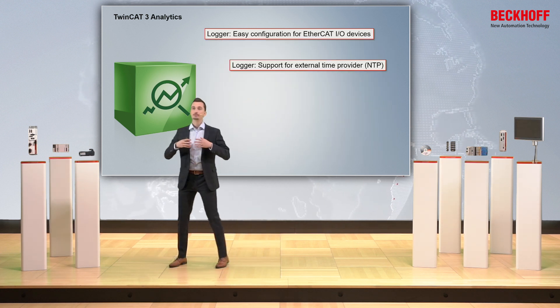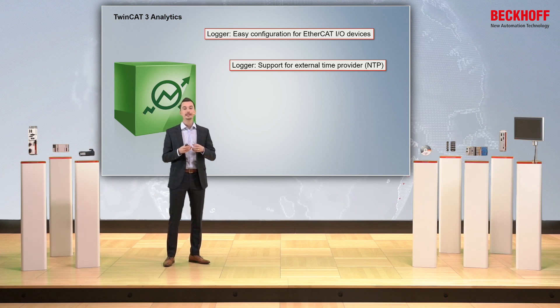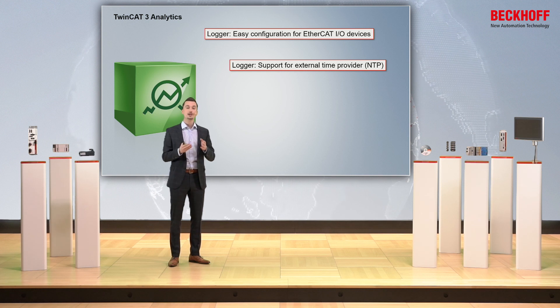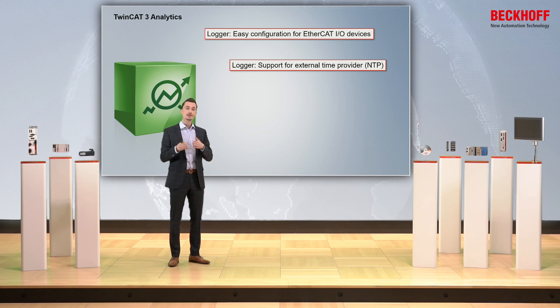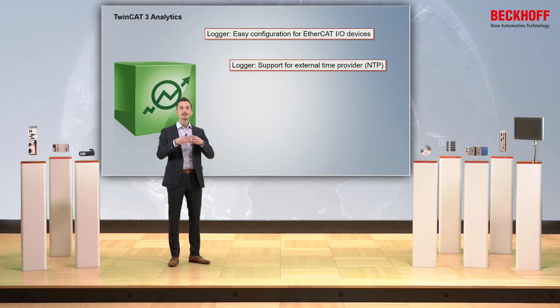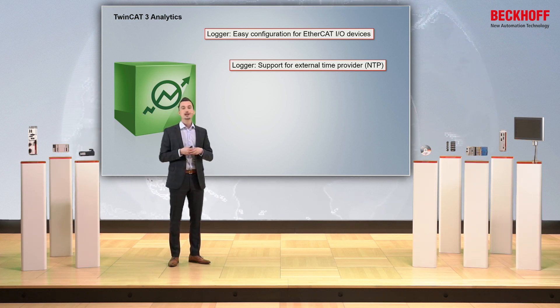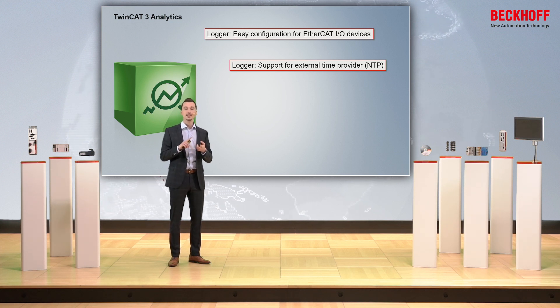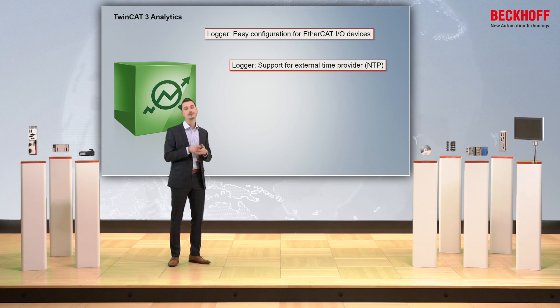In addition, and this is more or less a global topic for TwinCAT, we have integrated a workflow to automatically synchronize timestamps. Because if you have various machines connected to the same analytics logger, the timestamps need to be synchronized — only then is it possible to do analyses of different machines at once. In this case, we have added an external time provider which automatically corrects the timestamp with an offset. So only one reference clock is selected, and then all the timestamps are corrected according to this reference clock.